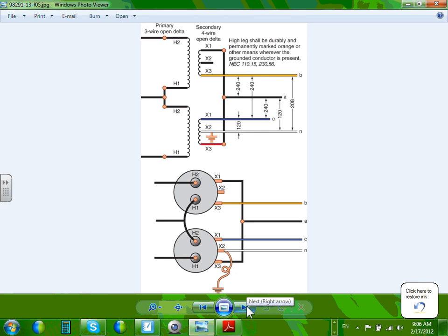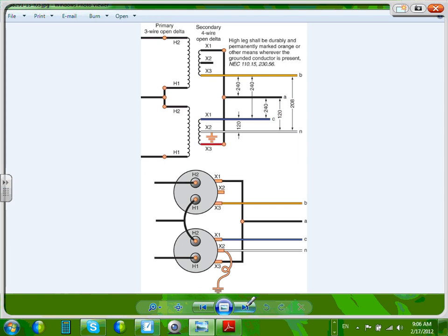You can have an open delta. I don't know if you see here. Here you can see how I lost one transformer, burned, got eaten. I continue to run at 4160 volt here, and rewire. Look how we rehooked it up to continue to get me the 240/120, which is center tap delta, center tap open delta. Can you guys see the tap here? Where the tap, that tap? It's called center tap open delta.